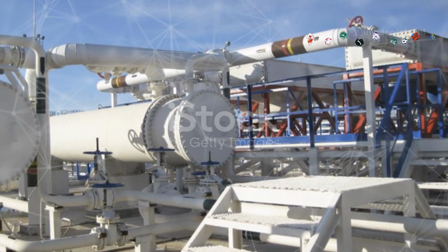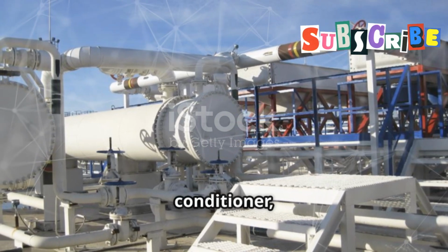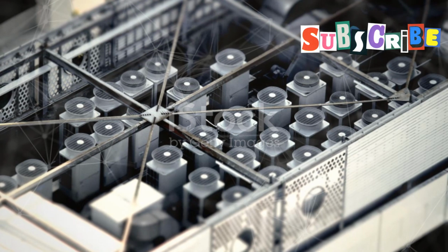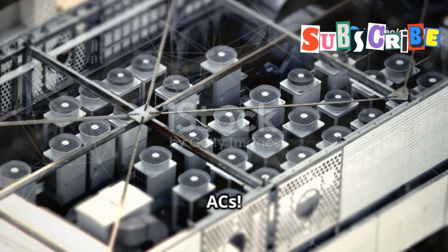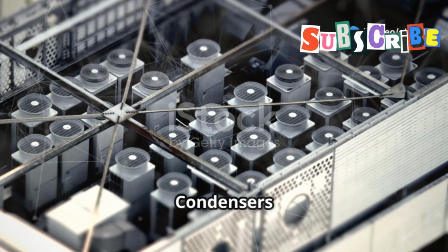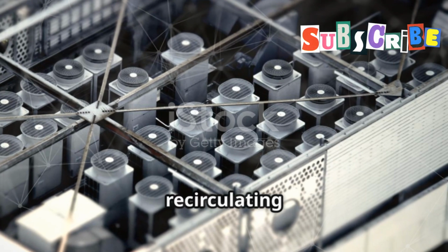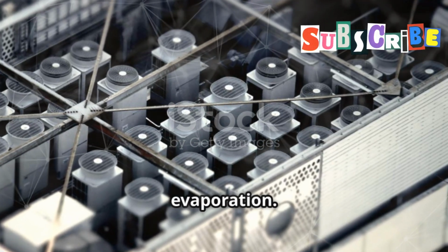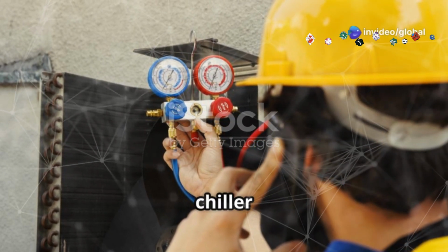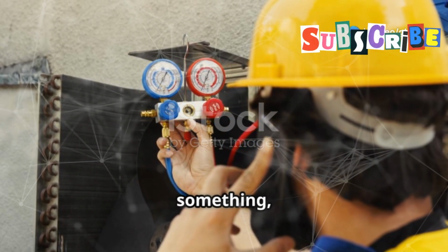Now, what's the difference between a cooler and an air conditioner? For a cooler to be an air conditioner, it must control temperature, humidity, air motion, and air purity. So, not all coolers are ACs. What about cooling towers and condensers? Condensers convert saturated vapor into liquid while cooling towers cool recirculating condenser water through evaporation. And lastly, what's a chiller? A chiller is a device for cooling something, typically part of a larger HVAC system.